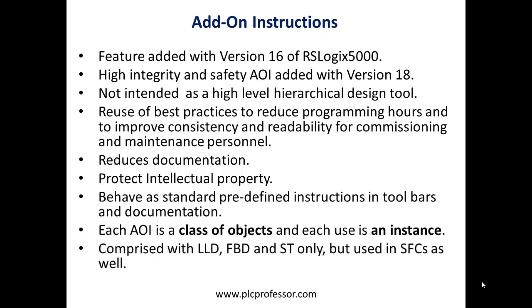Add-on instructions can be created with ladder logic diagram, function block diagram, and/or structured text, but never with sequential function charts — although they can be used in sequential function charts. To repeat: add-on instructions can be comprised of ladder logic diagrams, function block diagrams, and structured text, but not sequential function charts, though they can be used in sequential function chart programming.